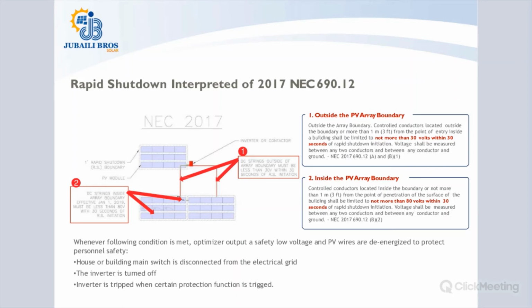Now, this is a facility that the PV optimizers can actually give you without you connecting an external rapid shutdown device. So if these are on the roof in a residential system, it is absolutely safe. You are assured that if there's any O&M or any firefighting to be done on the PVDC side, the system is absolutely in a safe shutdown state.